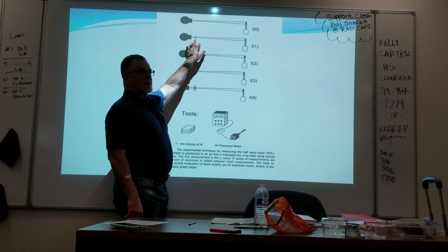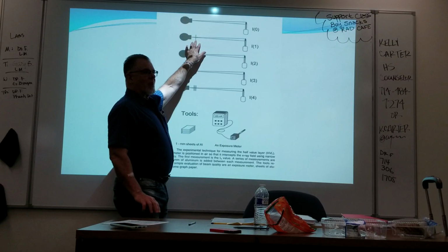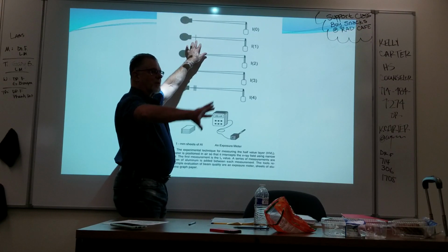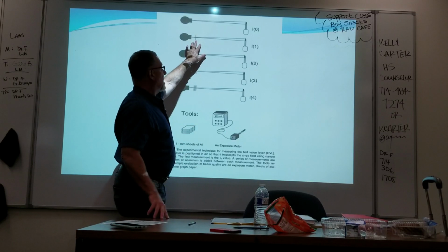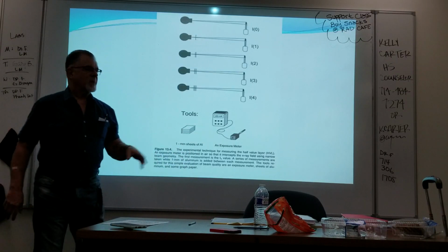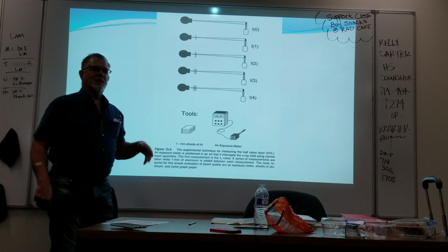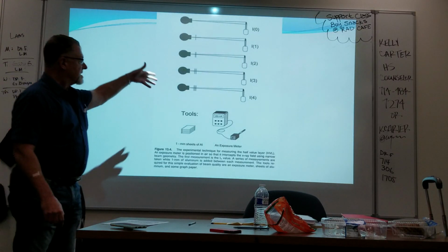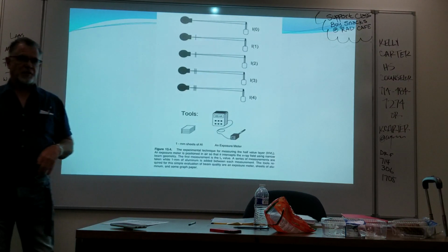What happens to your beam? It hardens it. So that starts what? Shifting the curve to the right slightly, not a lot, but ultimately if you start getting enough, yeah, it will shift a little bit. The error is small enough that we still call it half value layer. Okay? But that is the standard way to measure.